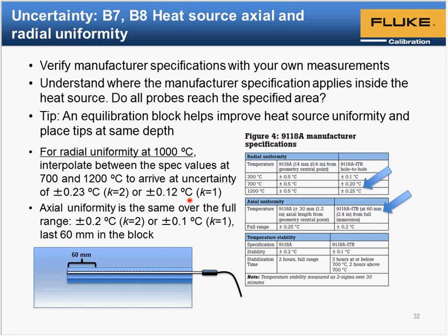You should make measurements yourself. You should never have blind confidence in these specs that we provide. In many cases, if you verify it yourself, you'll find that it's actually a little bit smaller. But you always want to check these numbers yourself to make sure the furnace is working correctly.